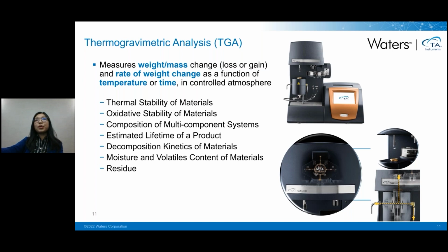It allows you to measure the thermal stability of the material. If you switch the gas to oxygen or air, you can also understand the oxidative stability of the material. As in the example I show you here with the SBR and CMC content, you can understand the composition of a multi-component system.